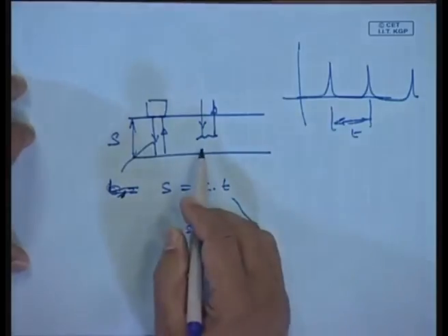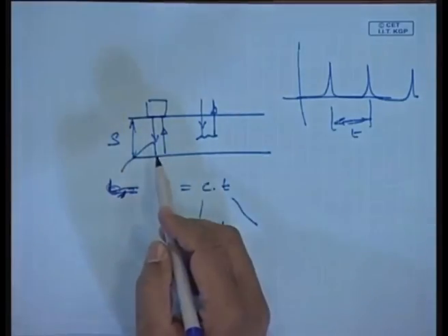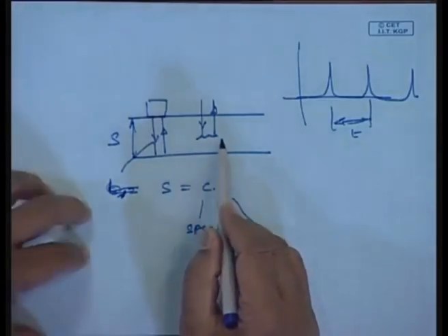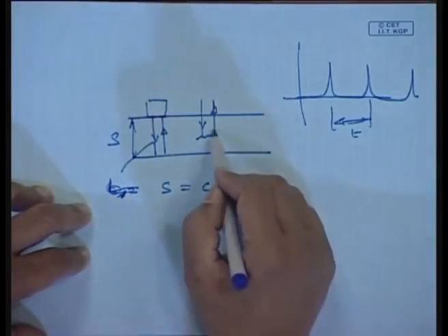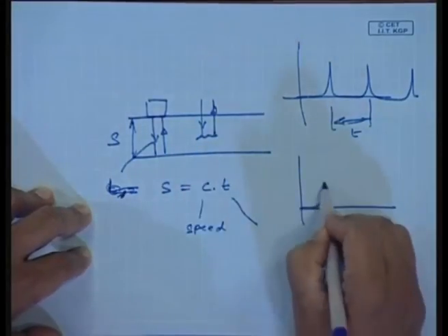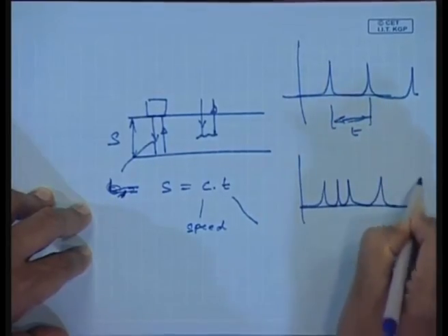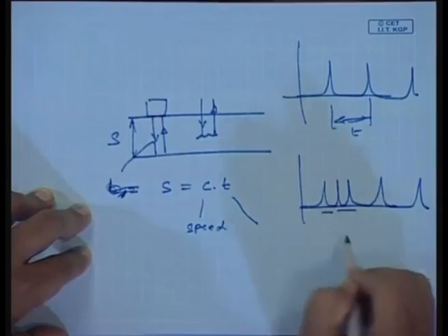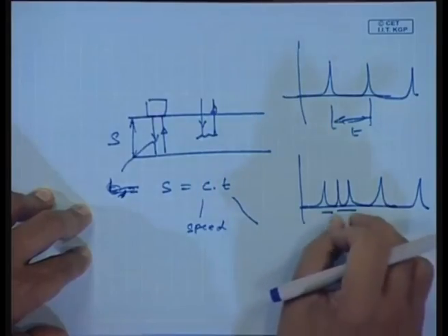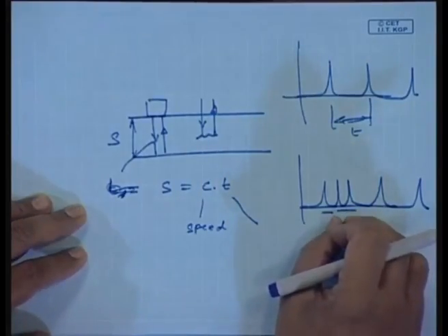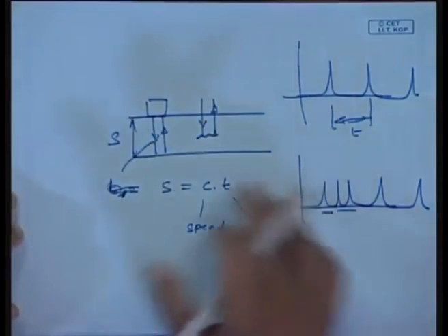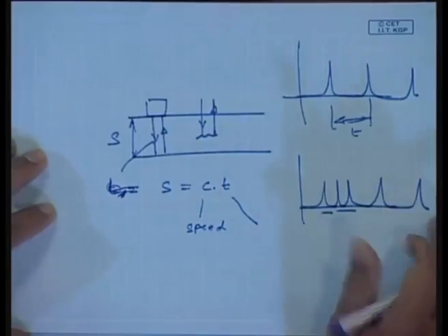This ultrasonic thickness gauge could also be used to detect cracks, as ultrasonic crack detectors, vice versa. You will see how much time it took. For example, if you are scanning and suddenly you see the time decreased, that means there is a shorter distance this wave has gone. So, there is a defect, an impedance mismatch, and that is the principle behind ultrasonic crack detectors.